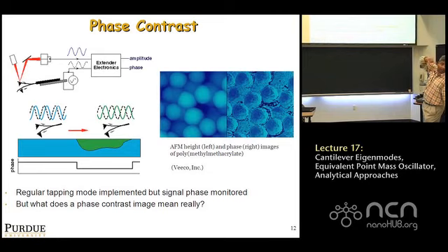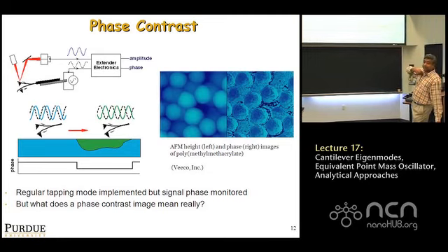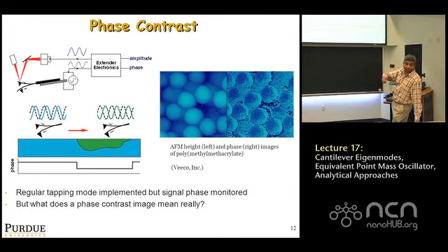That's the sine wave you're measuring, right? So you've got two sine waves. One sine wave goes in, the excitation, the dotted line. The output is the solid line, what you're measuring. There's a phase difference between the two, right?